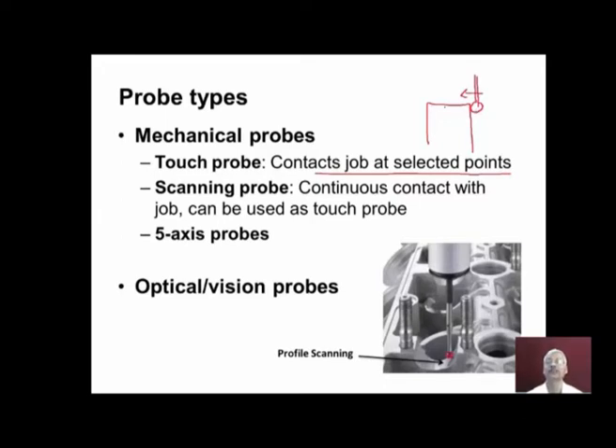If it is a CMM with a dedicated computer system, these selected points are decided by the software or the inspection program. Now the scanning probe, there is continuous contact of the probe tip with the job, but this can also be used as a touch type probe. And then we have 5-axis probes, the details of which we will be discussing shortly. And there is another type of probe called optical probe or vision probe. So you can see here this is a profile which is to be measured. So we have to select the scanning probe. It continuously moves over the profile, and then it will be sending the data points to the computer.